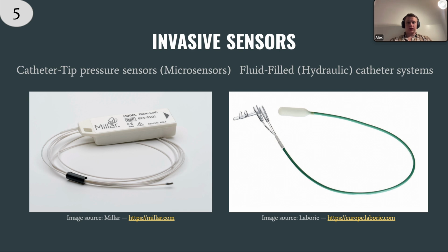But what's the difference? The difference is that these fluid-filled devices have a sensor outside the body, not inside the body. They're still invasive sensors because they do go inside our body, but the sensor itself is outside the body. Unlike the first type, catheter tip pressure sensors, where the sensor is inside our body, and it is considered more accurate than the fluid-filled type.